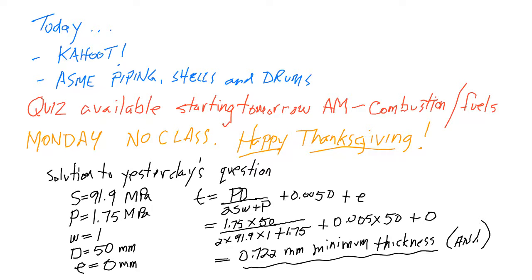So tube, yes, and pipe, yes, can be less than 6 millimeters thick. And the only time we're worried about pipe being at least 6 millimeters thick is if we've got a great big pipe that we're using for a shell. So if I order this material as 3/4 of a millimeter thick, that's a-okay. Easy to get stuck on that. 6 millimeters refers to plate, and plate is used for making shells. Plate is used for making tube sheets. Plate is used for making heads, so flat heads, formed heads that are hemispherical or ellipsoidal or something like that.